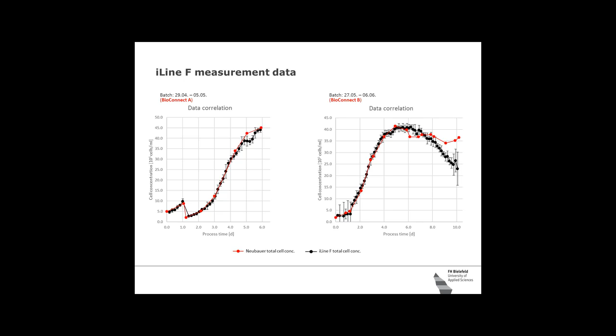So in summary, the iLine F system generates the numbers, and that's very important, automatically. It's an online measurement that is not consuming any sample. The sterility of the culture process was not affected, although we used the BioConnect longer than suggested by the vendor. It can be adjusted to the Cedex, to the manual cell counts, whatever you want, by one factor that has to be implemented. You can refocus the images, which would be very nice, I think, for FDA purposes.